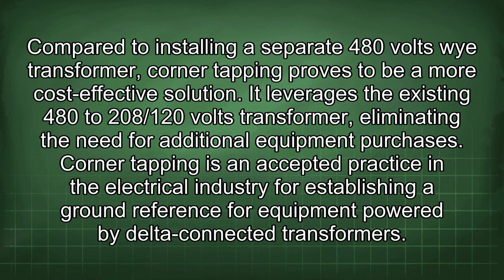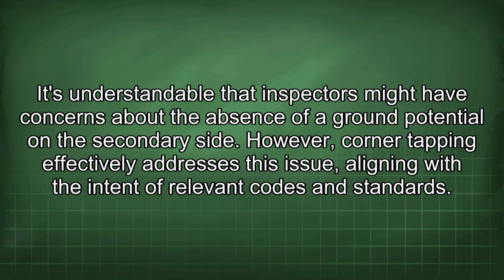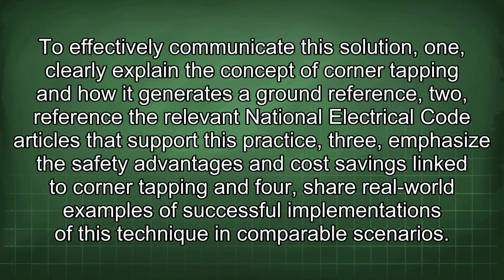Corner tapping is an accepted practice in the electrical industry for establishing a ground reference for equipment powered by delta-connected transformers. It's understandable that inspectors might have concerns about the absence of a ground potential on the secondary side. However, corner tapping effectively addresses this issue, aligning with the intent of relevant codes and standards. To effectively communicate the solution: 1. Clearly explain the concept of corner tapping and how it generates a ground reference. 2. Reference the relevant National Electrical Code articles that support this practice. 3. Emphasize the safety advantages and cost savings linked to corner tapping. And 4. Share real-world examples of successful implementations of this technique in comparable scenarios.